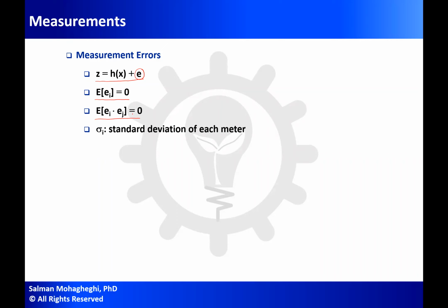Now, every meter itself is going to have a standard deviation of error, which would indicate how much these errors of measurements at different measurement instances disperse around 0. If, for example, I'm looking at the error of measurement, let's say 0 means there is no error and the measurement is 100% exact, this would be an ideal case. But imagine you have a meter that in one measurement has this much of error, so positive error, in another measurement has some negative error, another negative error, and then another positive error. Then I can define a standard deviation of error associated with this distribution of errors around 0.